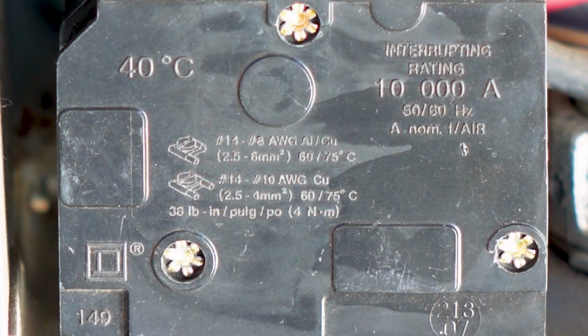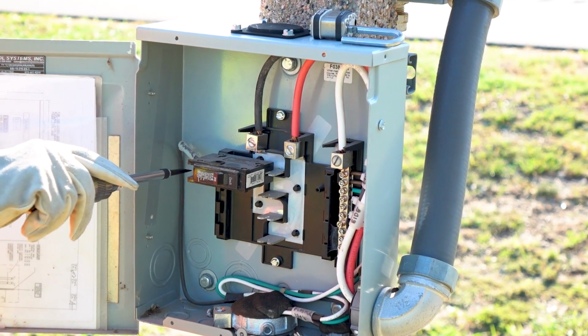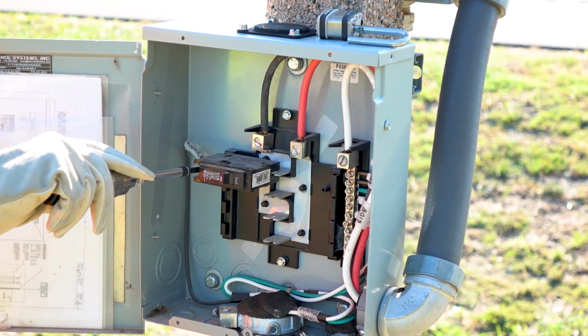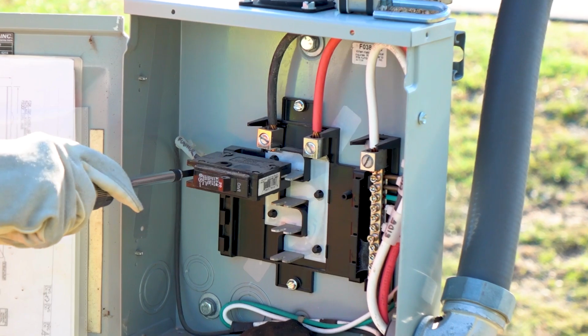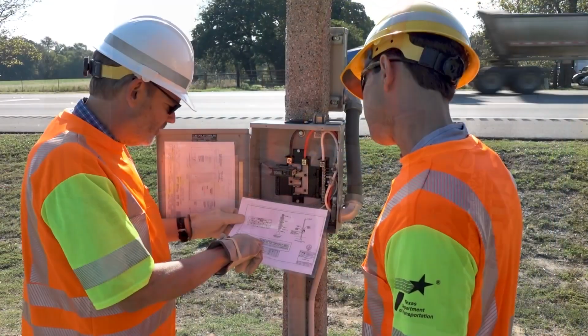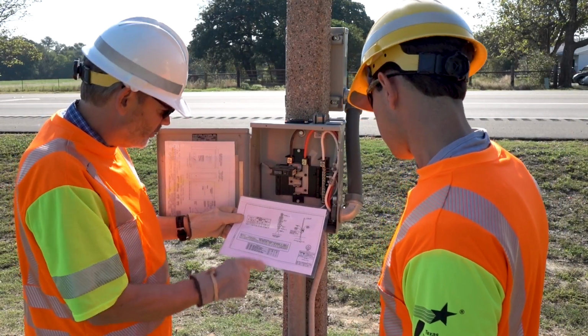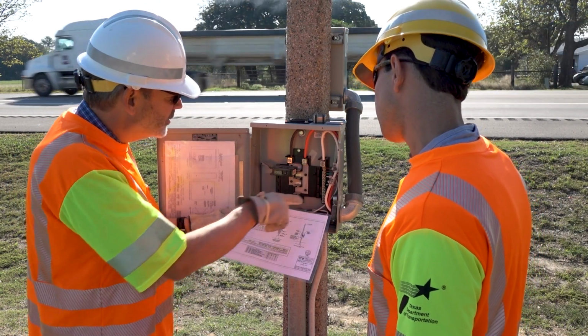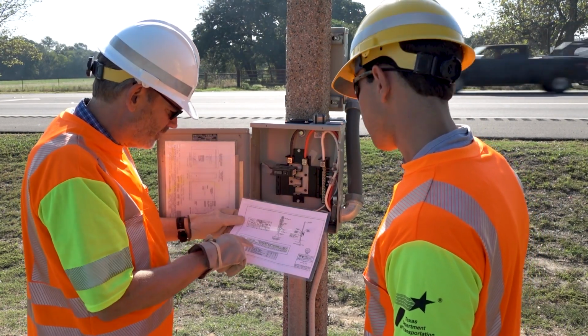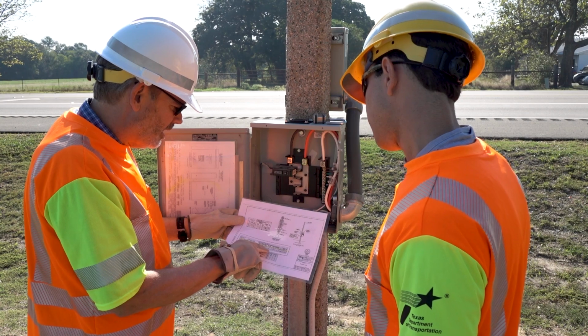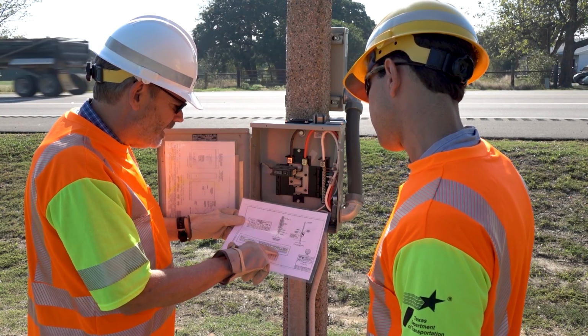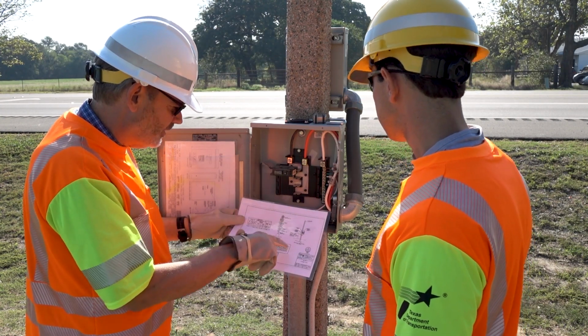Each branch circuit breaker will have a label showing the required torque value for the conductor connection to the breaker. This should be checked and verified with a torque screwdriver to make sure each conductor has been properly secured to the breaker. At this point in the inspection, the inspector will review the electrical service data sheet in the plan set, verifying that the quantity and size of the branch circuit breakers matches the plans.